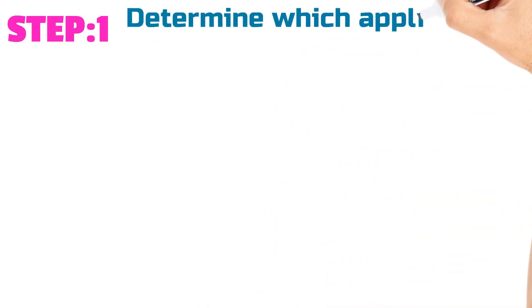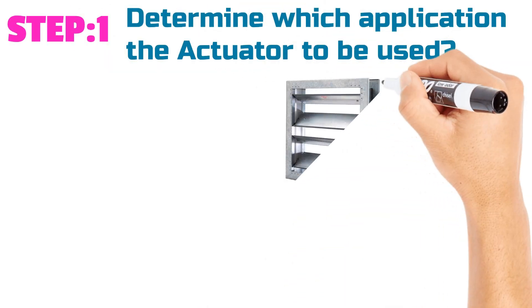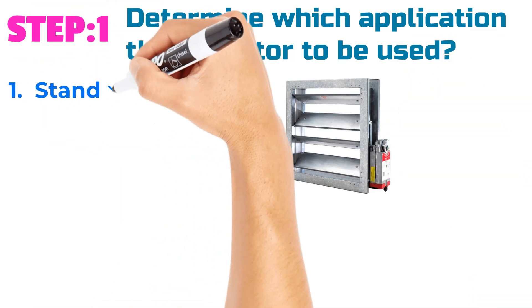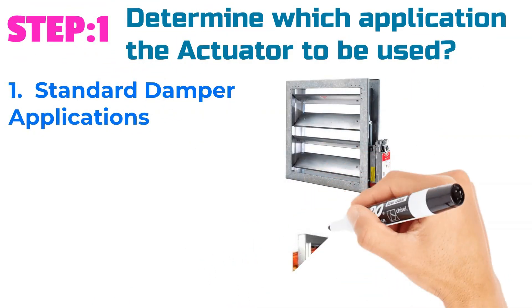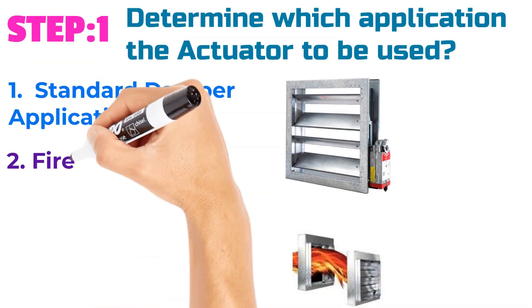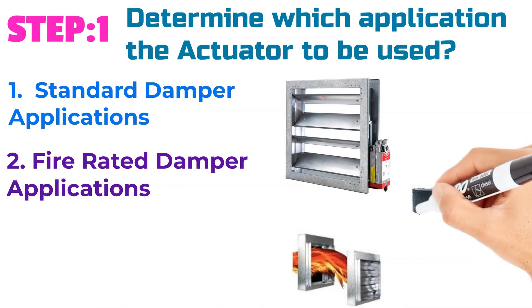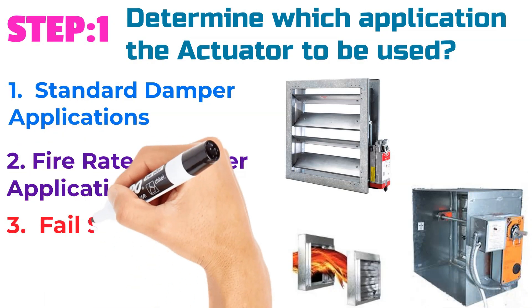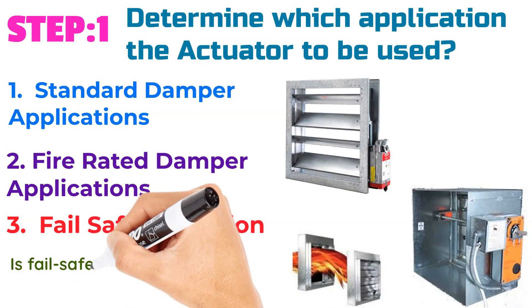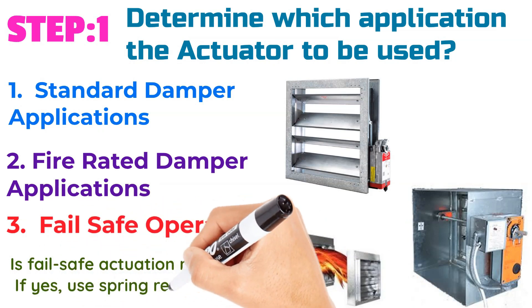Step number one: Determine which application the actuator is to be used in. One — standard damper applications. Two — fire rated damper applications. Three — fail-safe operation. Is fail-safe actuation required? If yes, use a spring return actuator.